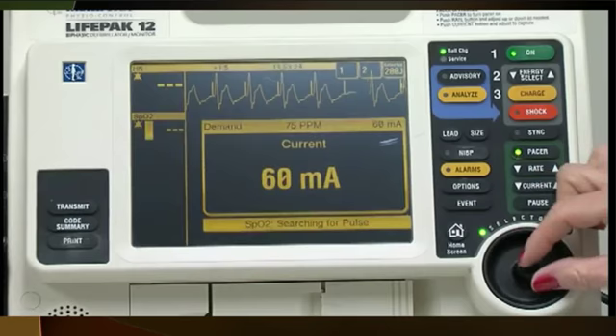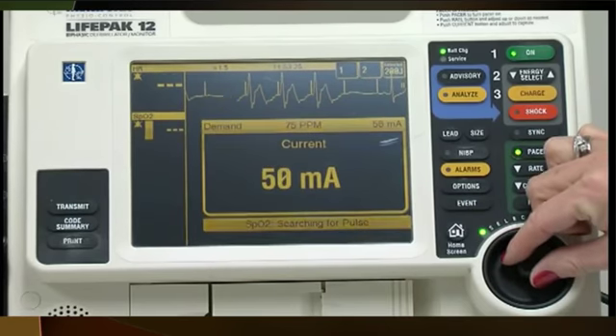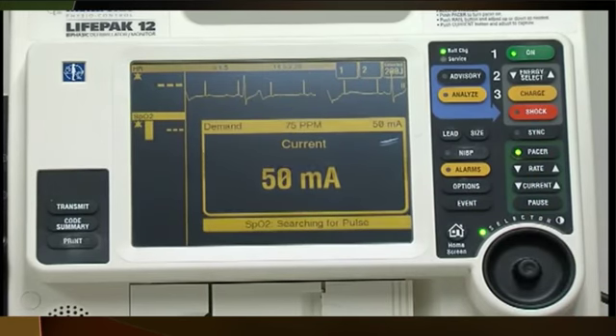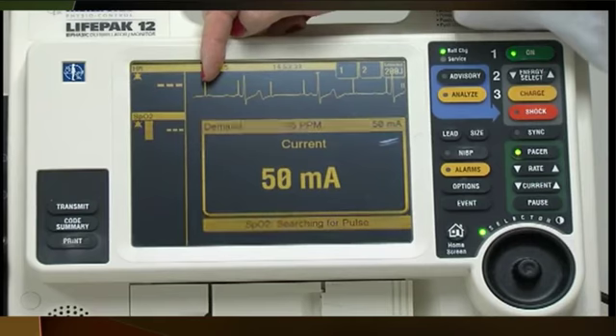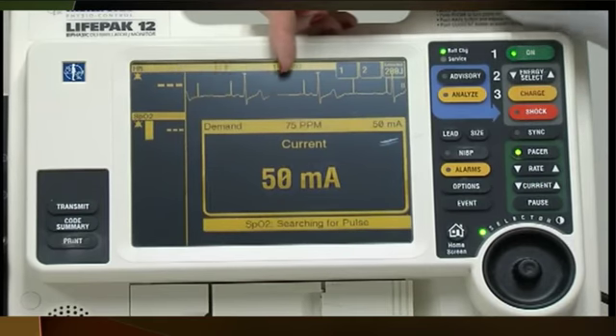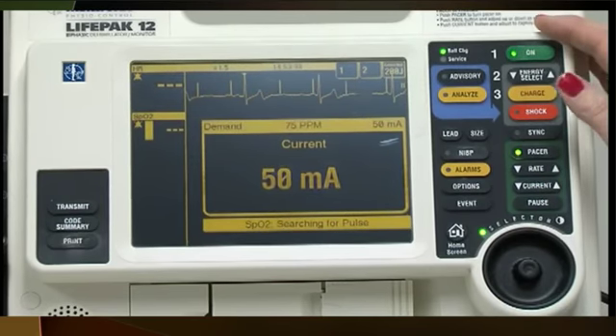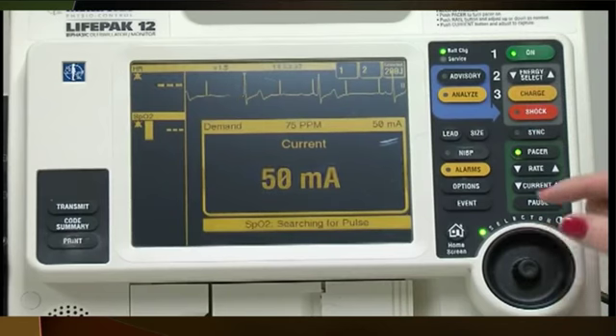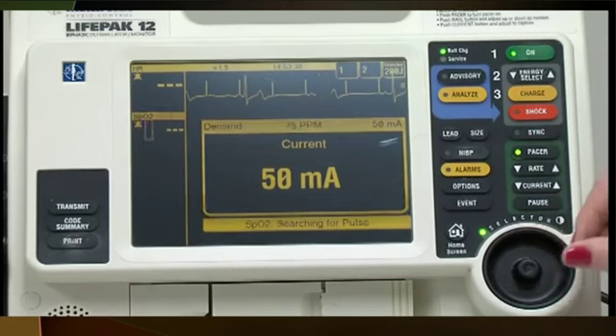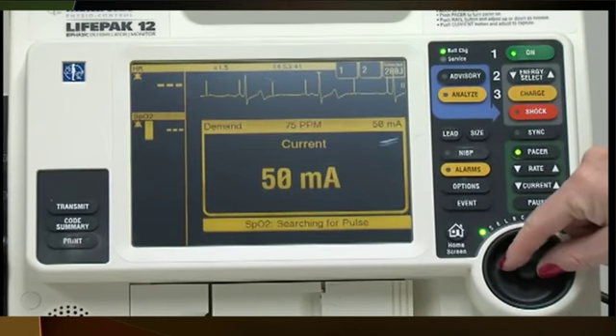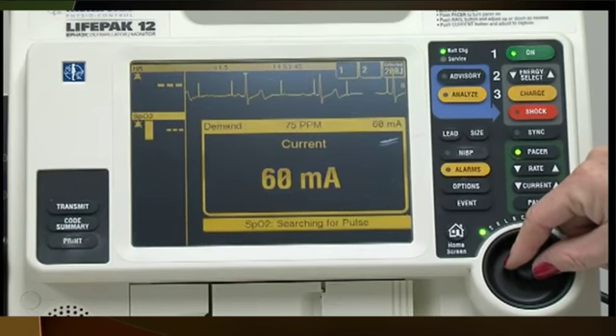So we're going to decrease our milliamps, and I've lost one-to-one capture. You can see the spikes with no contraction after it. So that means I have lost that stimulation. What we need to do next is to increase our milliamps until we regain that one-to-one capture. So I'm going to keep going up with my milliamps.